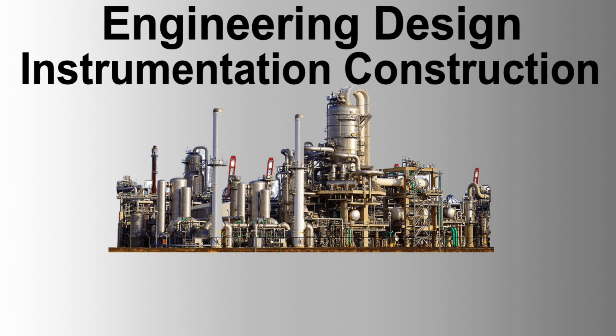The installation of instrumentation shall be performed by fully qualified and competent tradepersons, skilled in the particular field of work in which they are engaged, together with a suitably qualified and responsible engineer or supervisor experienced in the installation and testing of hazardous area equipment. Where applicable, the contractor shall engage the services of a specialist subcontractor to ensure the equipment is correctly installed and commissioned with guarantees maintained. All trades personnel that install tubing and compression fittings shall have completed a manufacturer's training course in the correct procedure for the installation of that manufacturer's tube compression fittings.